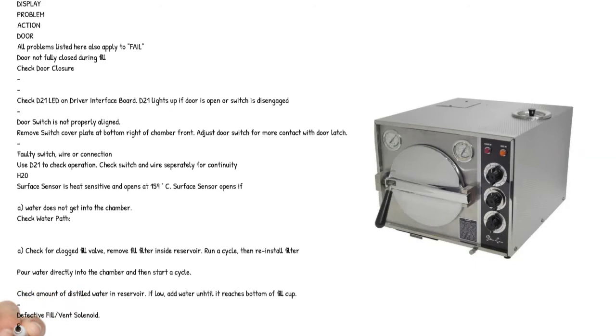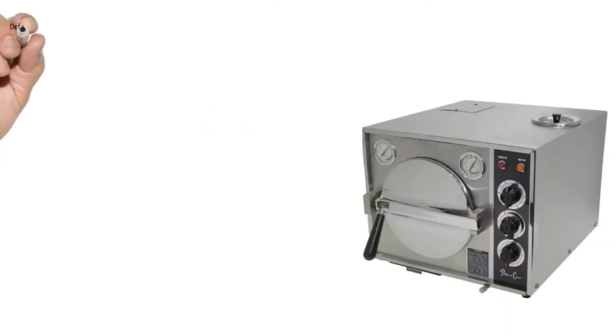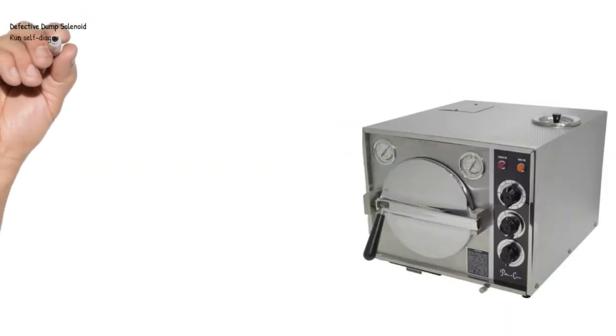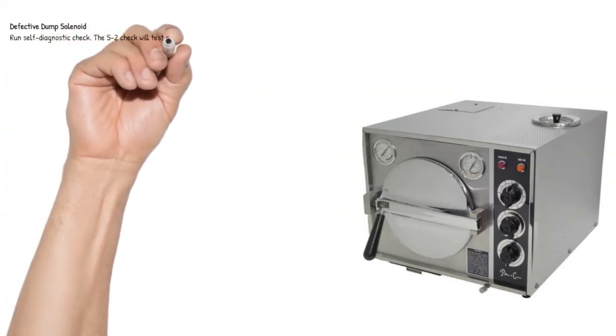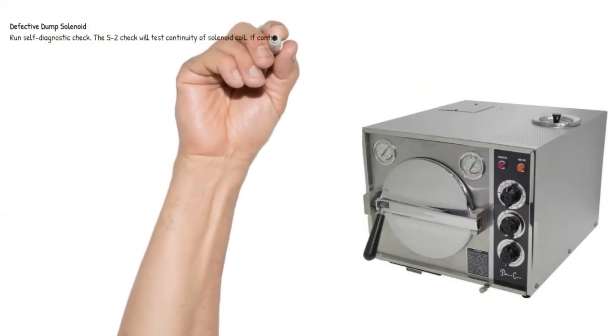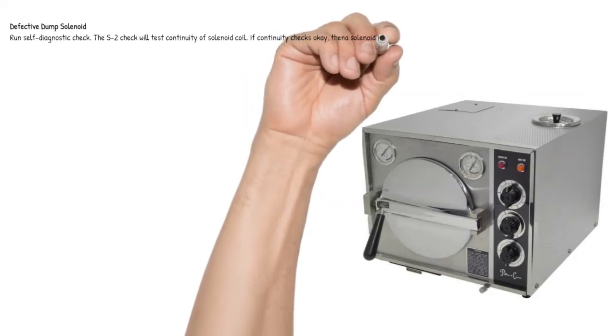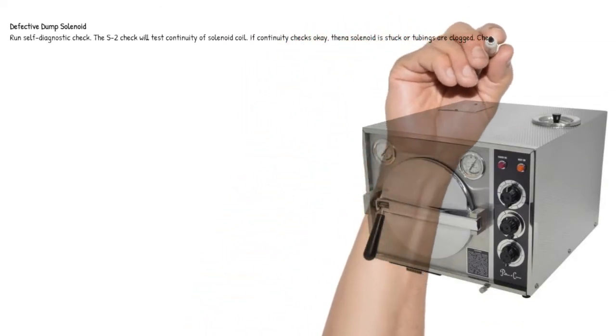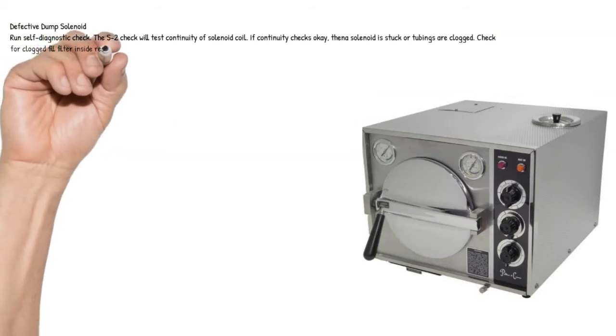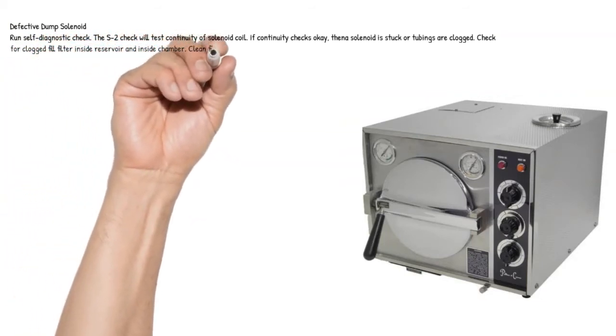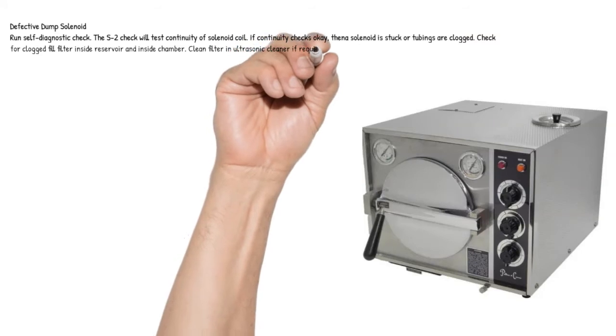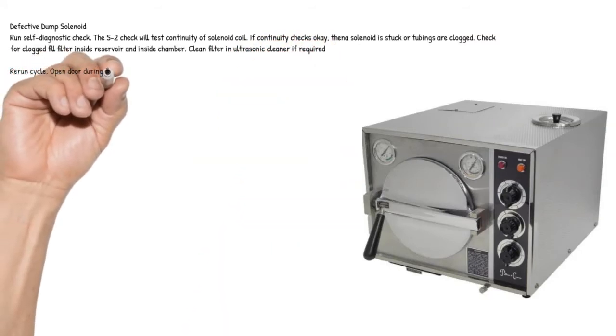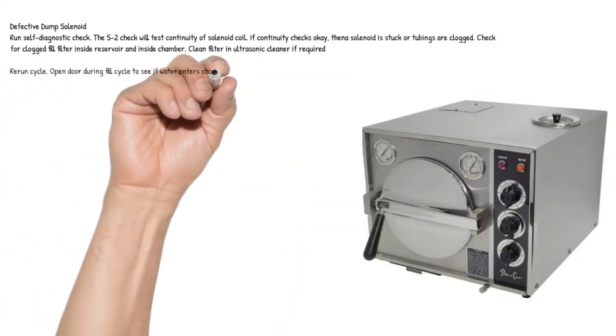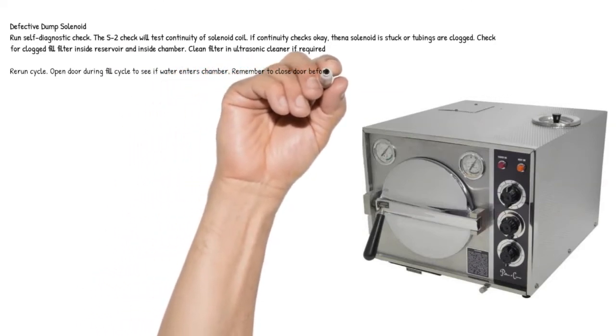Defective fill/vent solenoid. Run self-diagnostic check. The S1 check will test continuity of solenoid coil. Defective dump solenoid. Run self-diagnostic check. The S2 check will test continuity of solenoid coil. If continuity checks OK, then a solenoid is stuck or tubings are clogged. Check for clogged fill filter inside reservoir and inside chamber. Clean filter in ultrasonic cleaner if required. Rerun cycle. Open door during fill cycle to see if water enters chamber. Remember to close door before fill cycle is complete.